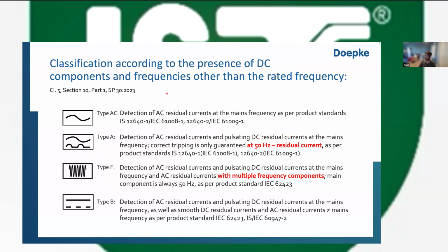So if we talk about the type AC RCD, this is an RCD that can only detect alternating current residual current at main frequency as per their product standard. The type A is an RCD that can detect AC residual currents and pulsating DC residual currents as per the main frequency. And correct tripping is only guaranteed at 50 Hz of residual current.